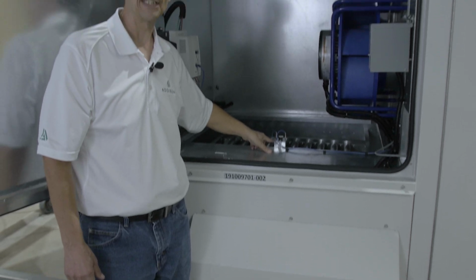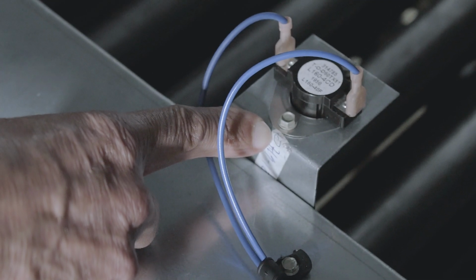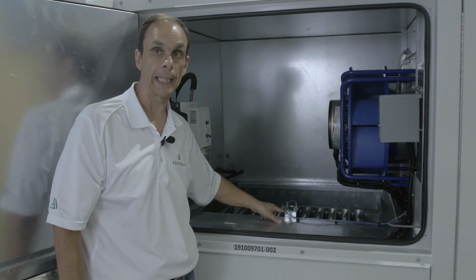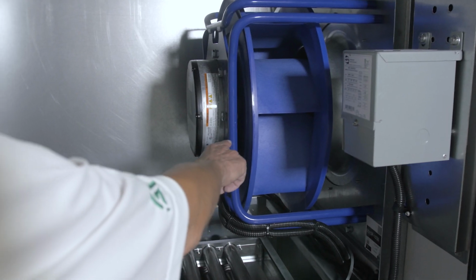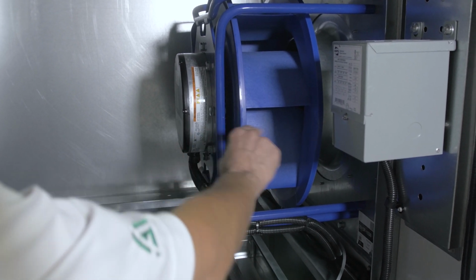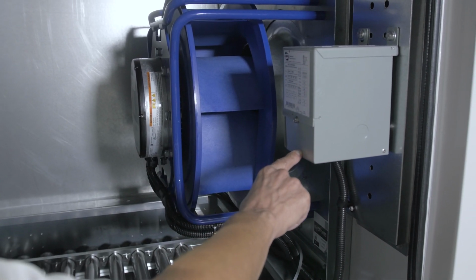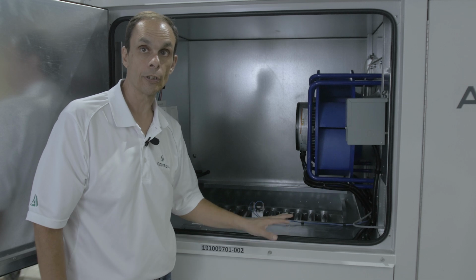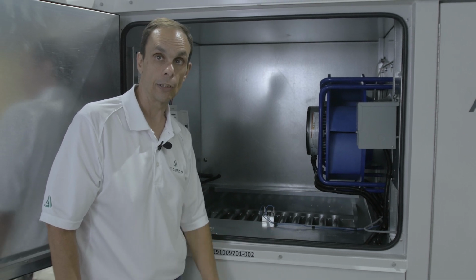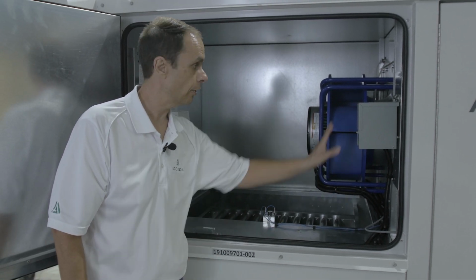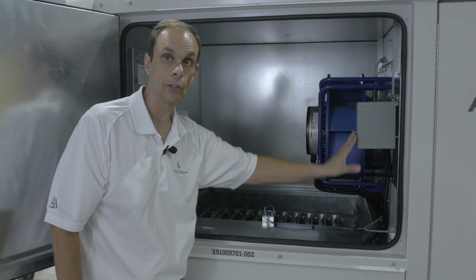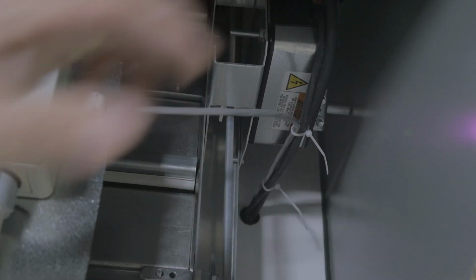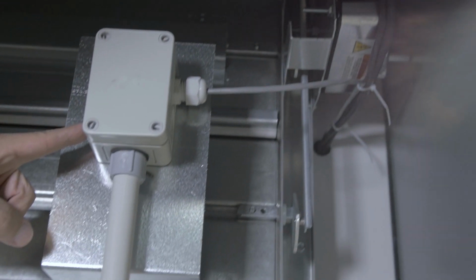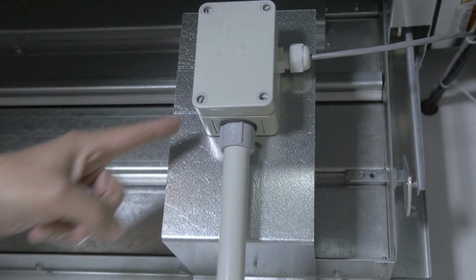Inside is your BCTL high limit, so if the supply fan should ever stop running, this will help kick off the gas heat as a safety. Here's your supply fan, and then here's the step-down transformer to help run the controls to 230 volts. So this is a 460 volt unit, and the gas furnace is 230 volts, so this will step the voltage down from 460 to 230 volt. Outside air damper actuator, outside air temperature, and RH sensor.